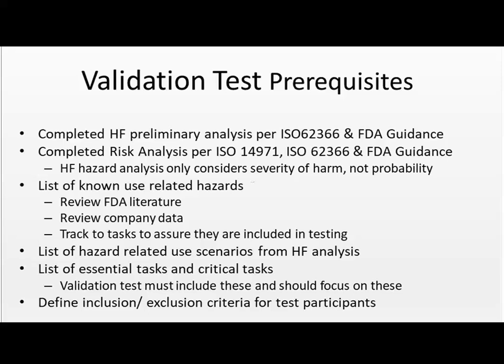You should have a completed risk analysis following ISO 14971, keeping in mind that human factors hazard analysis considers only severity of harm, not probability. FDA feels you cannot reasonably estimate the probability of a person committing an error.